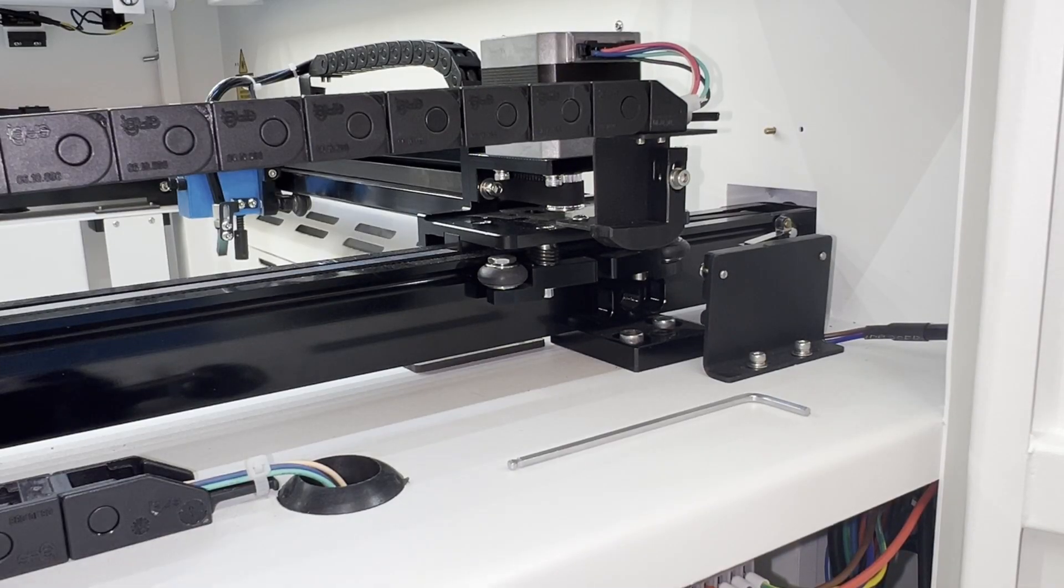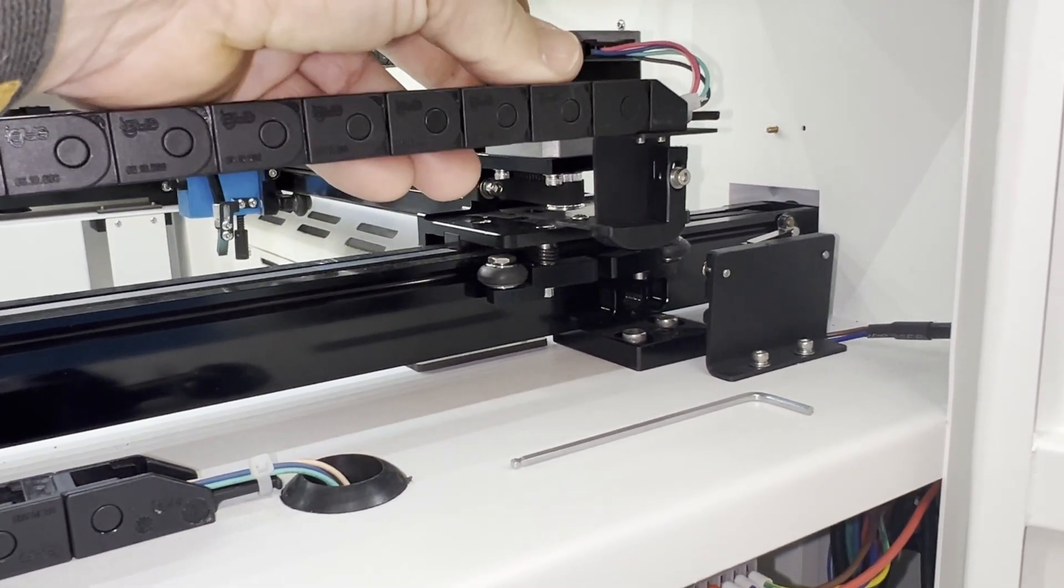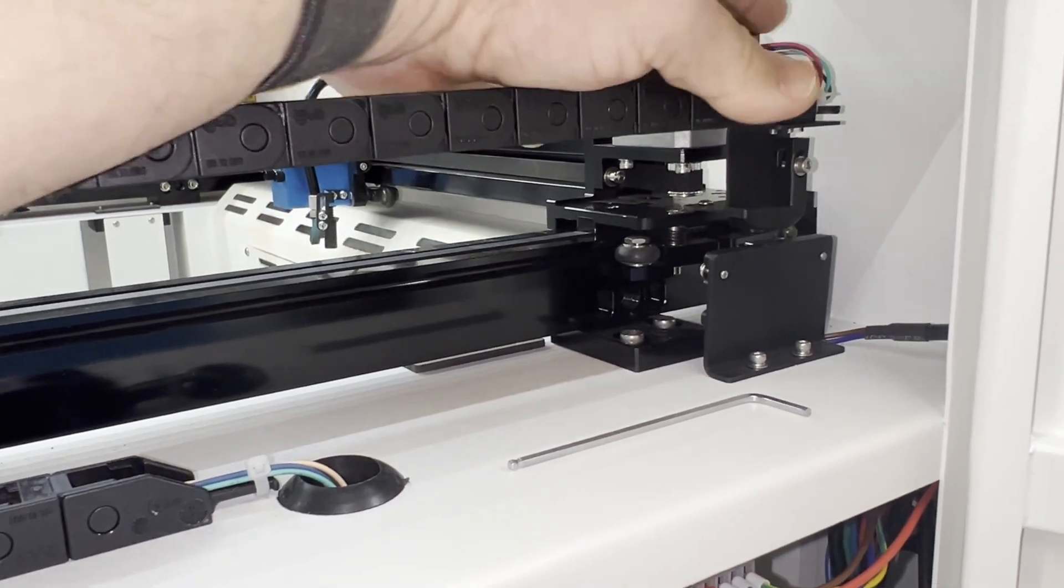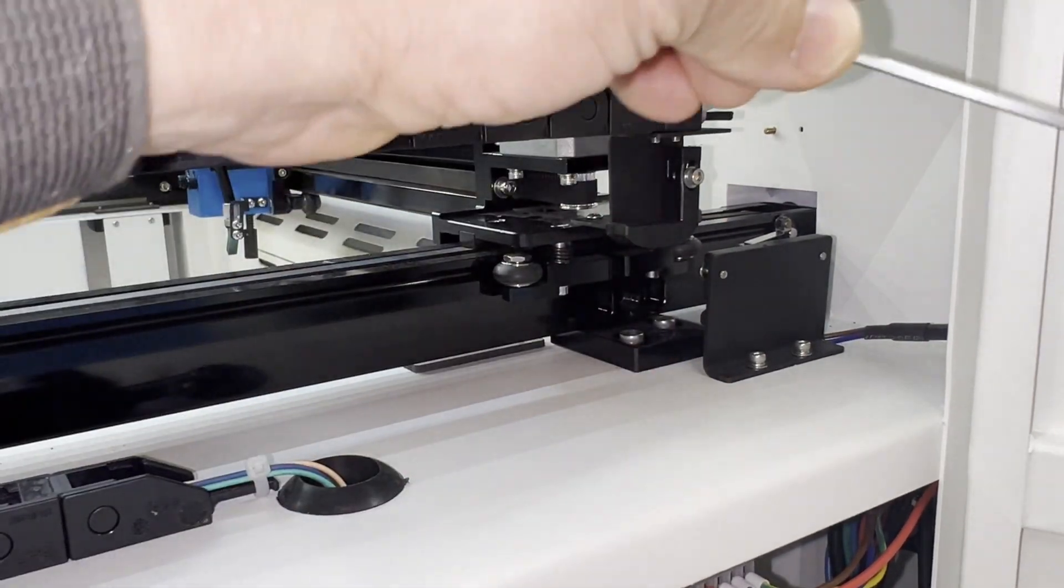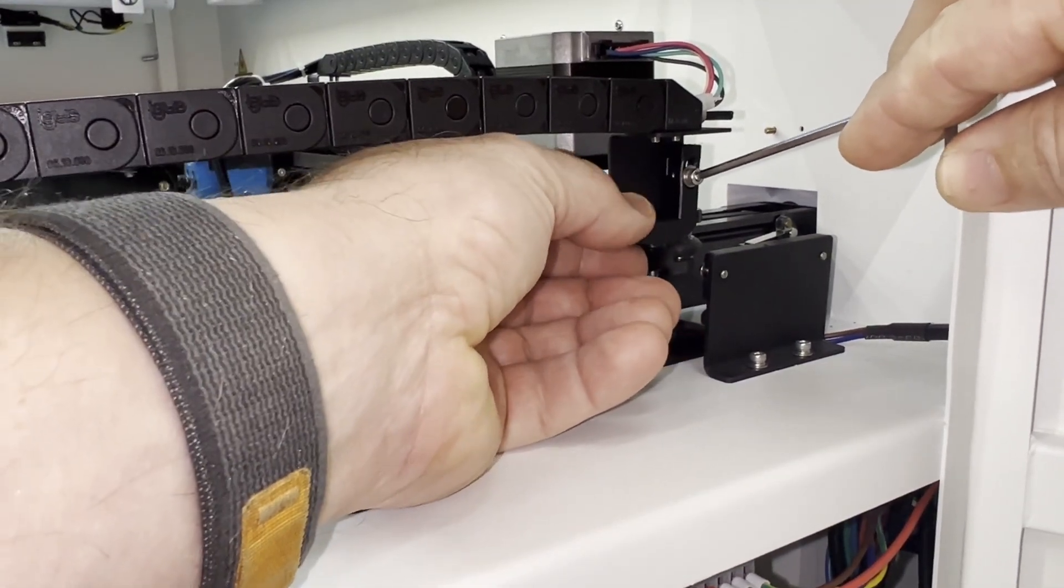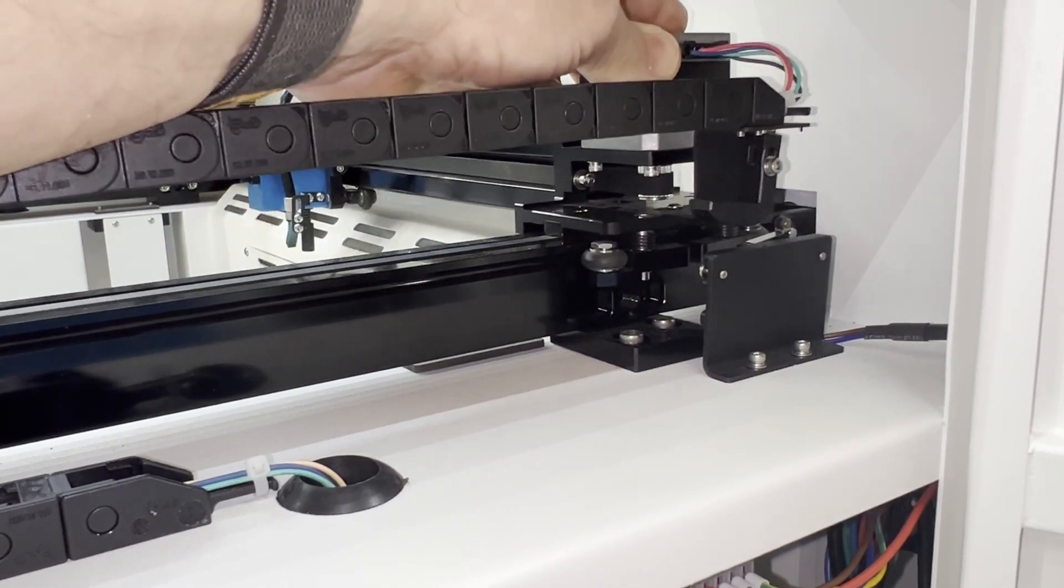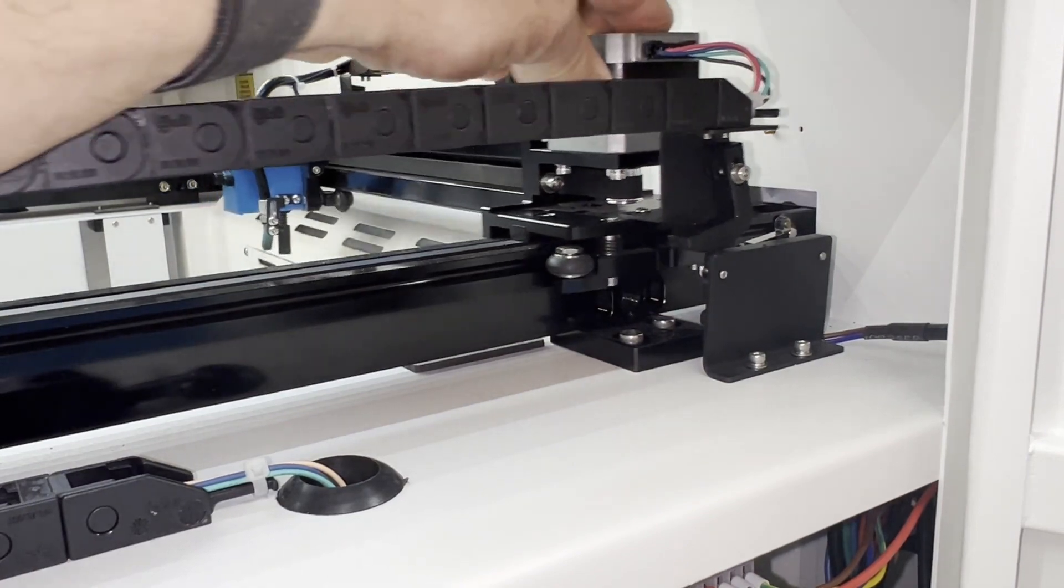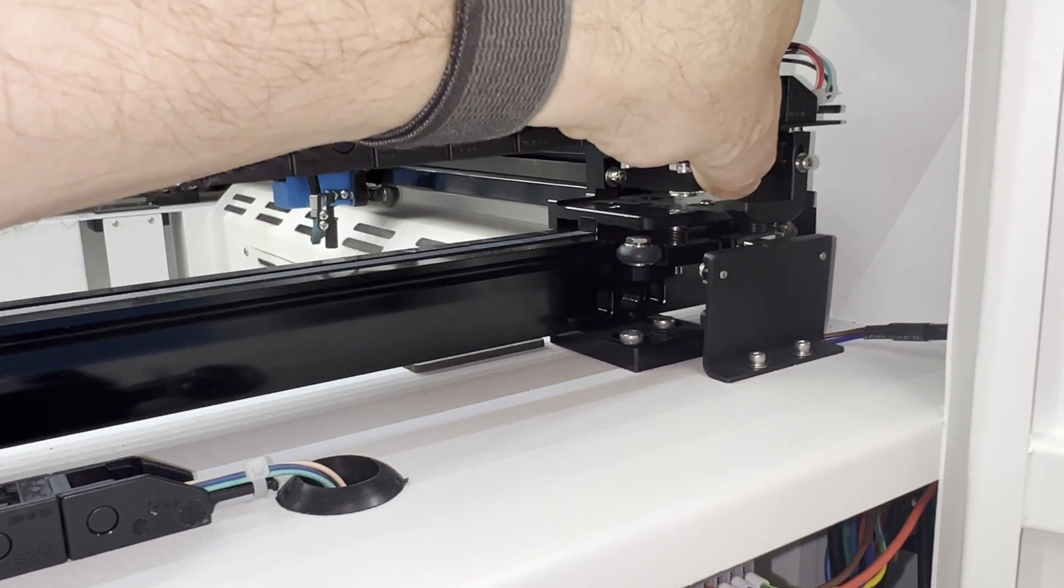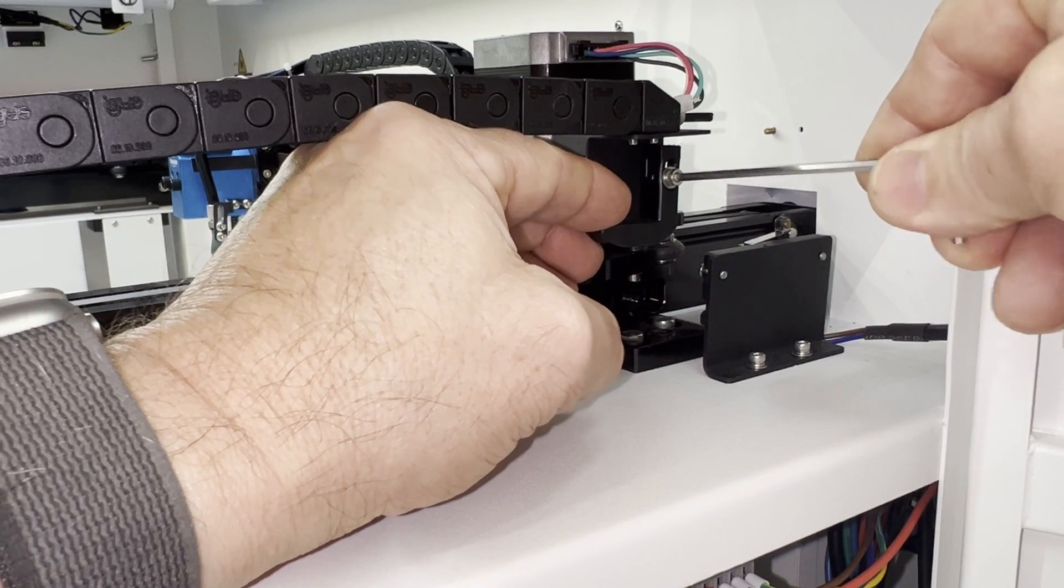And I'm going to show you how to do that real quick. So one thing I want to note is that I did turn off the power. If we do not turn off the power, we cannot move this freely. You'll find resistance when you try to do this. And it's just much easier to move this and make contact and adjust with the machine off. Now, using your Allen key, you are able to loosen this adjustment. So let's say it was adjusted well out of position and you were not able to make contact. You can see that it is touching it, but it is not clicking the switch. So you would loosen it up a little bit, kind of push it back. And you can hear it triggering the switch.